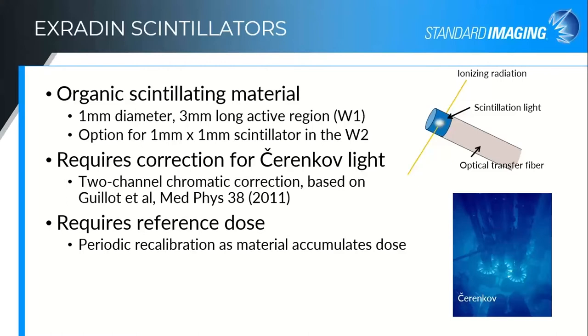The difficulty with scintillators is that you do produce Cherenkov light in that optical transfer fiber. This manifests as a stem effect — a different amount of additional optical signal based on the amount of stem, the amount of that transfer fiber, that's in the field. We use a two-channel chromatic correction method to remove the Cherenkov from the measurement channel, based on a publication by Guillot et al. from Medical Physics a little over ten years ago.